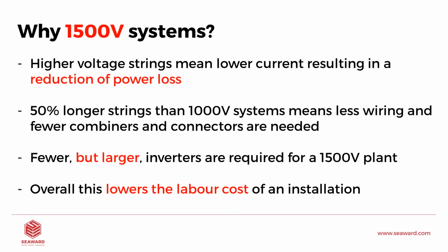So I mentioned earlier that we are moving to 1500 volt systems, and of course, I don't think we'll be moving backwards from that. But why are we actually doing that? Well, higher voltage strings means we can actually lower the current, and that results in a reduction of power loss on the PV system. So they're actually a lot more efficient. 50% longer strings than 1000 volt systems mean we have a lower balance of system costs. So we have less wiring, fewer combiner boxes, fewer connections. And this really helps us take a lot of cash off the price per kilowatt or per megawatt.